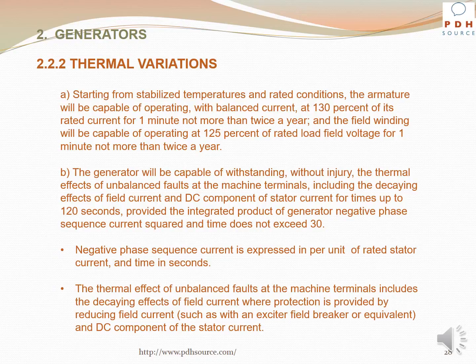provided the integrated product of generator negative phase sequence current squared and time does not exceed 30. Negative phase sequence current is expressed in per unit of rated stator current and time in seconds. The thermal effect of unbalanced faults at the machine terminals includes the decaying effects of field current where protection is provided by reducing field current, such as with an exciter field breaker or equivalent, and DC component of the stator current.